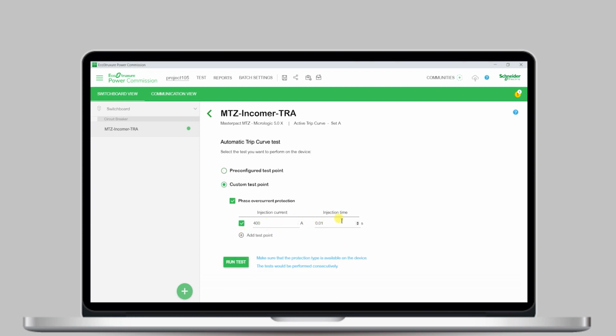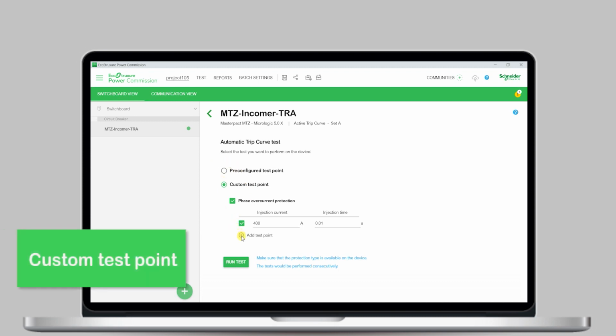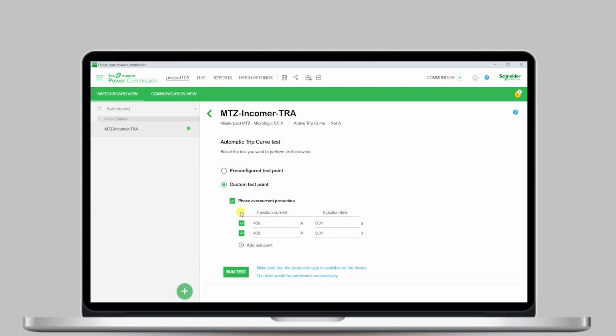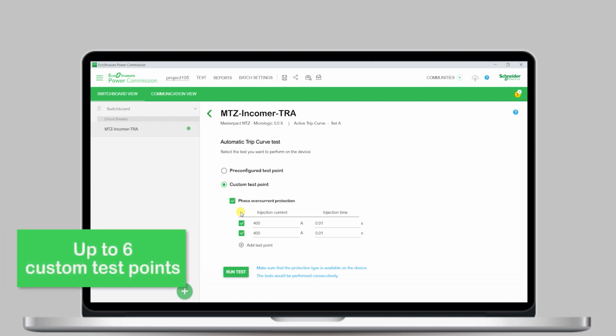Alternatively, you can also choose a specific injection current and time of injection as a custom test point of the overcurrent protection curve, LSI. In this case, the software will inject the current for the duration entered and will show if a trip occurs or not along with the trip time. It will not show any pass or fail result, but the result will also be available in the report. You can add up to 6 such custom test points for each breaker.